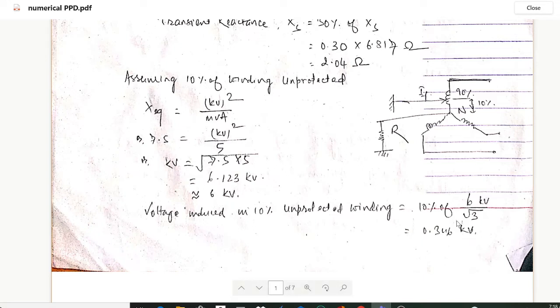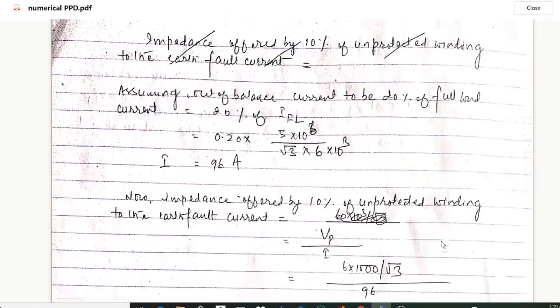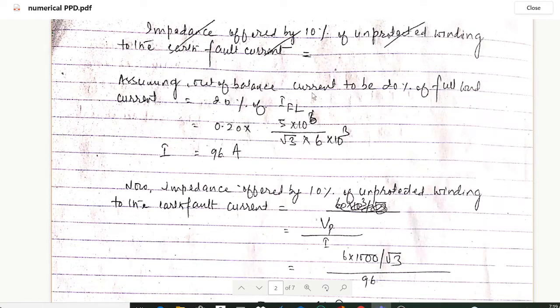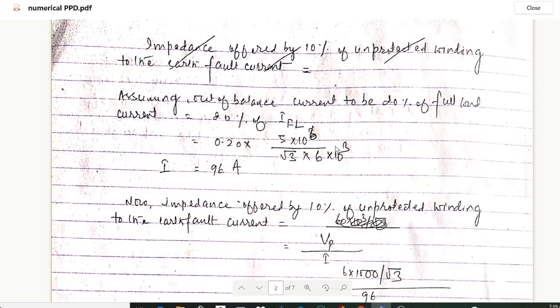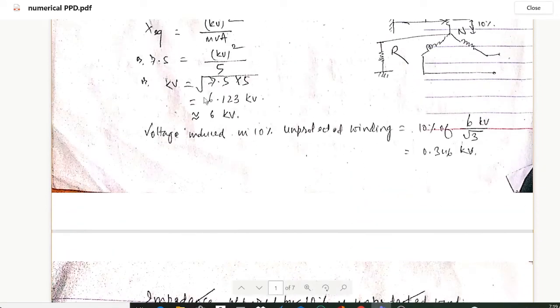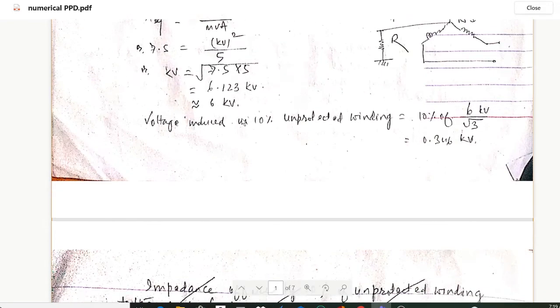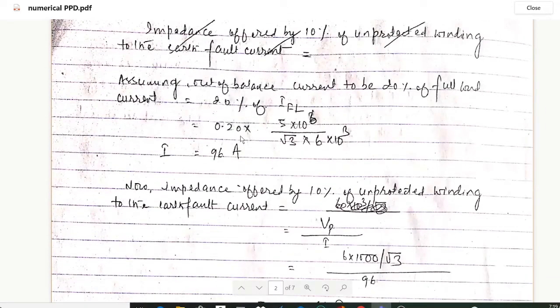Now assuming out of balance current to be 20 percentage of full load current, it will be 0.20 into full load. In order to calculate the full load we have 5 MVA given, so 5 MVA means 5 into 10 to the power 6 upon root 3 into 6 kV. 0.20 into 5 into 10 to the power 6 upon root 3 into 6 into 10 to the power 3. So we will get the value of out of balance current, so value of I will be 96 amperes.